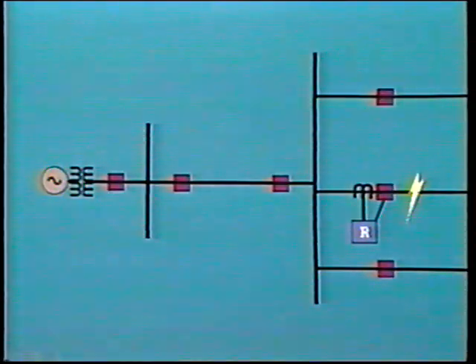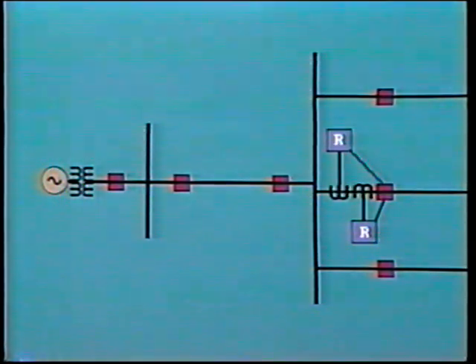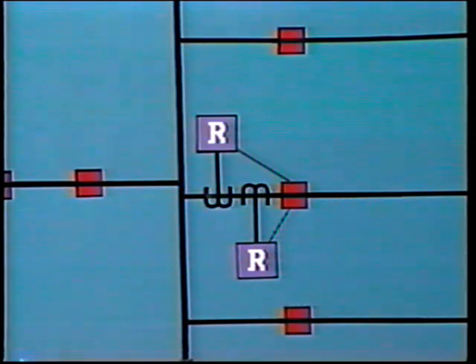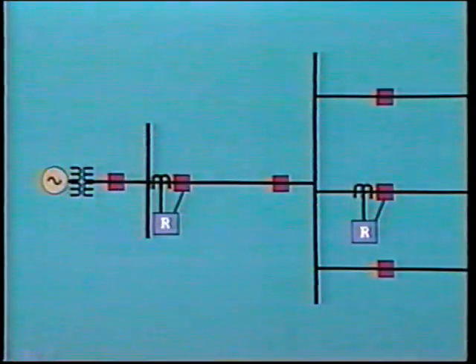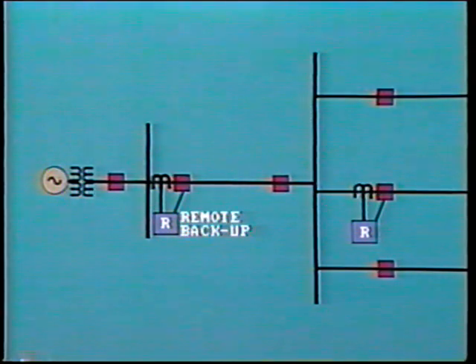If a relay fails to operate and hence clear an intolerable fault, then equipment damage may occur, and certainly there would be a system upset. For this reason, it is customary to install additional or duplicate relays to provide backup. If the backup relays are installed in the same station as the primary relays, this is known as local backup. Sometimes backup relays are located at a remote station, and this is called, logically, remote backup.